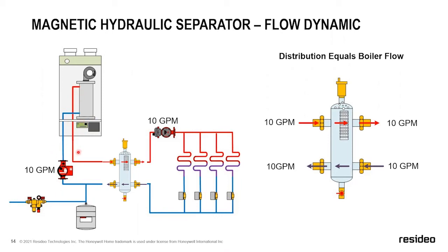So what a lot of boiler manufacturers will do is they'll say, well, I've got 100,000 BTUs of output. I want to see a minimum of a 20-degree delta T. So using some math that I've explained in other training classes that we've done, you want to see 10 gallons a minute to deliver that 20-degree temperature differential across a boiler that's doing 100,000 BTUs. So I'll use this 10 gallon a minute example for a few.